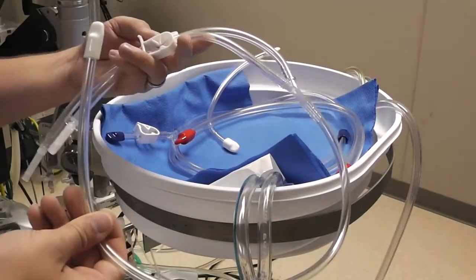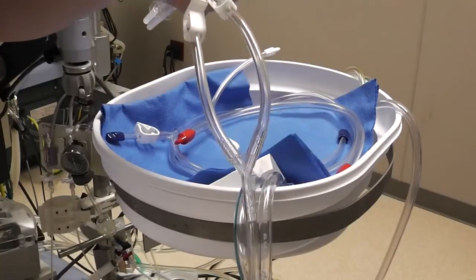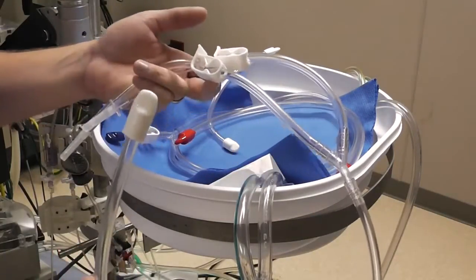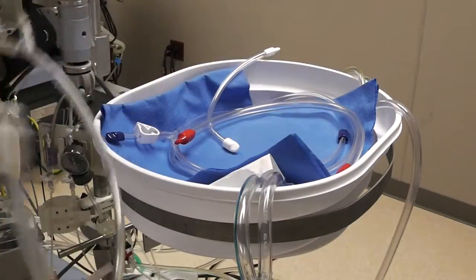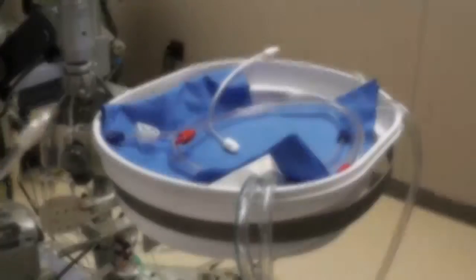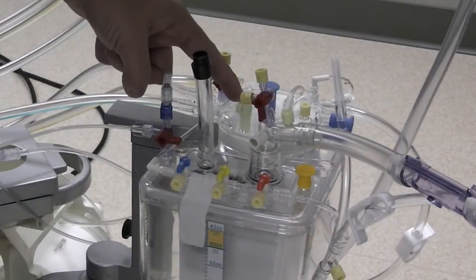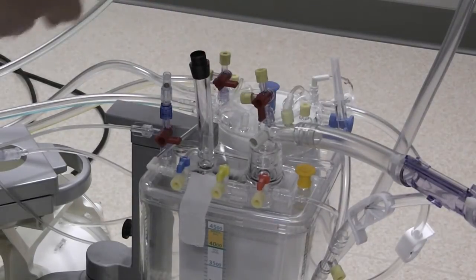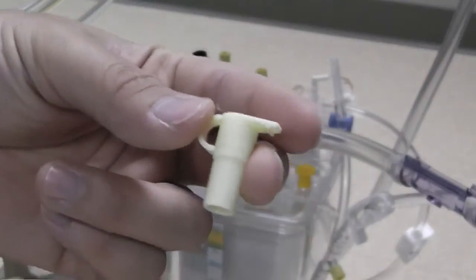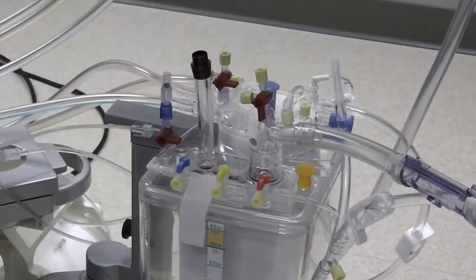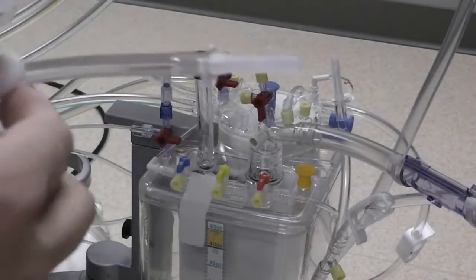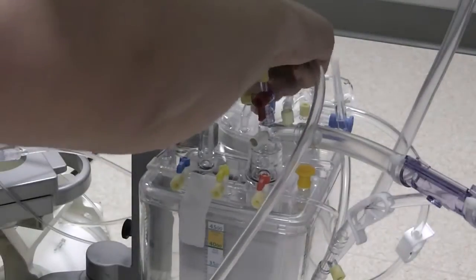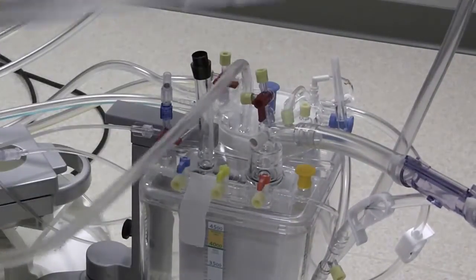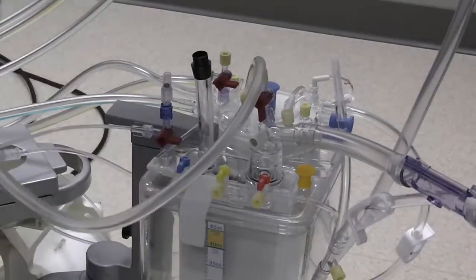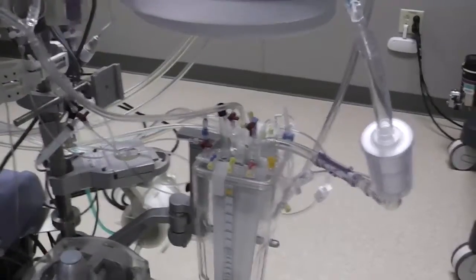Now we're going to take our fill line, which is split with a Y like this. It has a white cap on it, and it splits into 2 lines. And we're going to make that connection to the top of the cardiotomy. So hopefully you can see this here, but this is the connection for that line. Let me pull this cap off here. You'll see this is sort of a different kind of cap, so you can just pull the whole thing off, but it also opens up here. That's how you know that's the correct cap. And we're just going to take the white cap off of this end and connect it there. And now these ends are going to be tucked under the blue cloth on top.